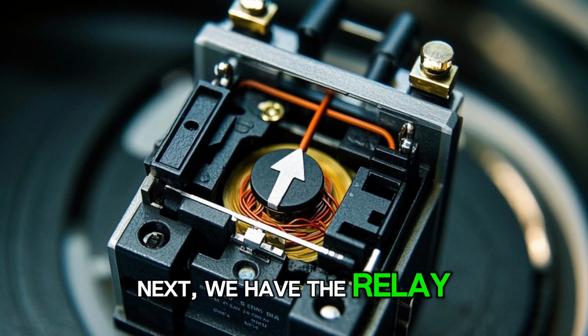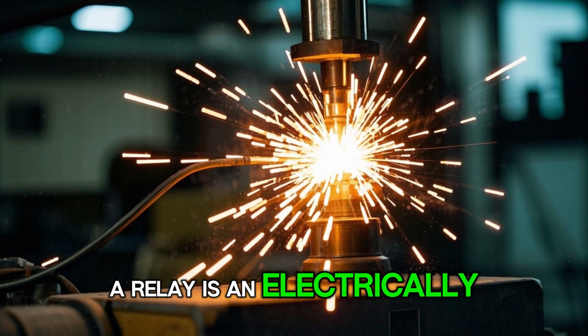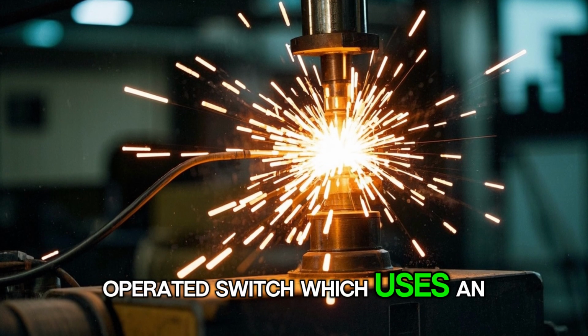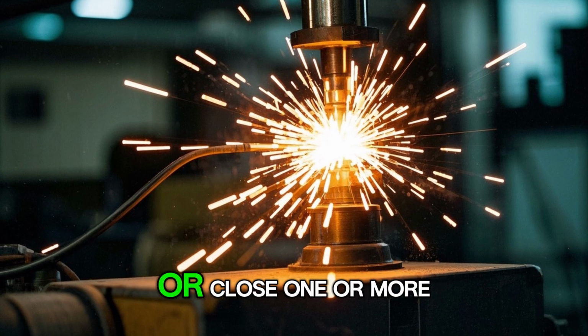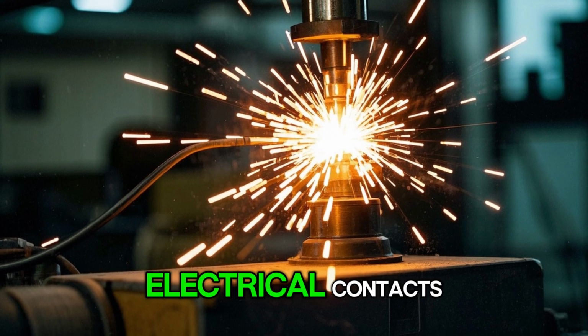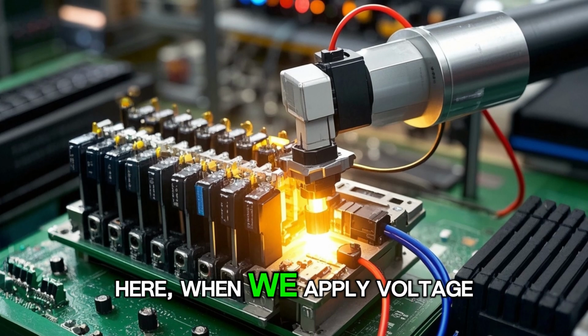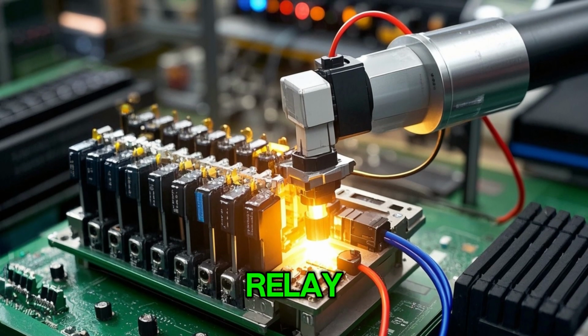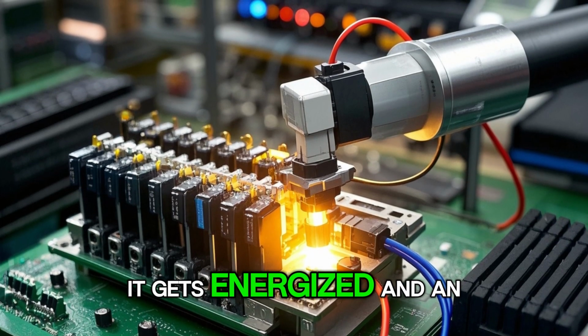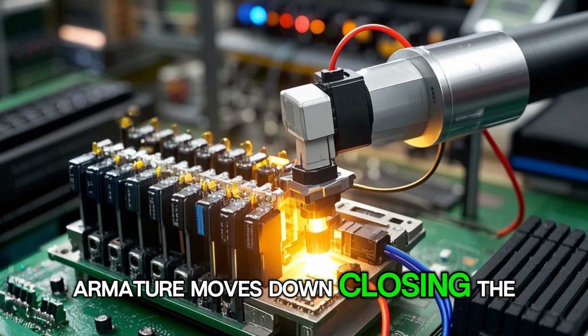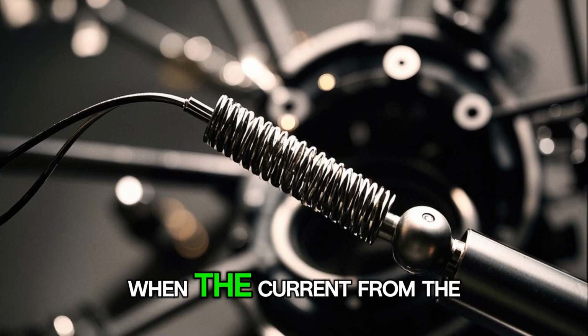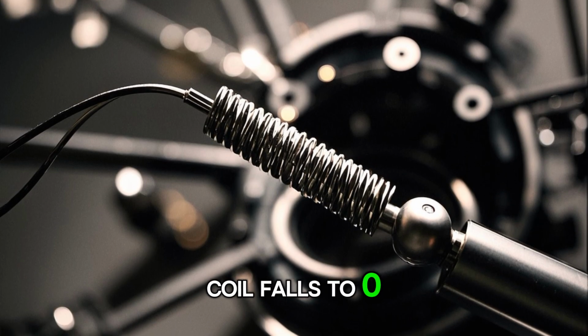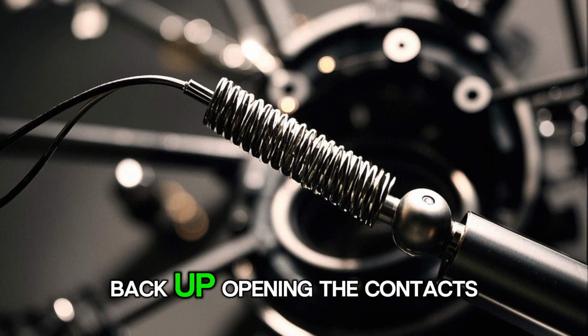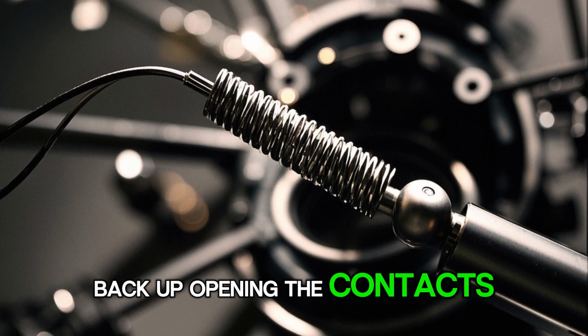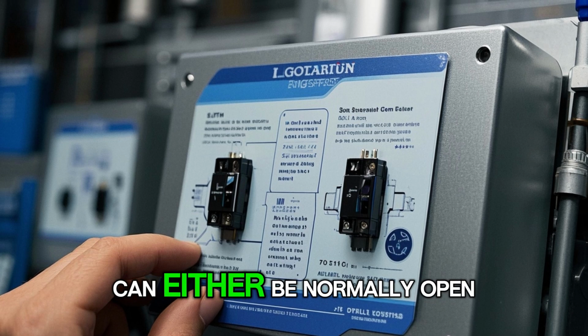Next, we have the relay. A relay is an electrically operated switch, which uses an electromagnet to open or close one or more electrical contacts. Here, when we apply voltage to the coil of the relay, it gets energized, and an armature moves down, closing the switch contacts. When the current from the coil falls to 0, the spring brings the armature back up, opening the contacts. The contacts of a relay can either be normally open or normally closed.